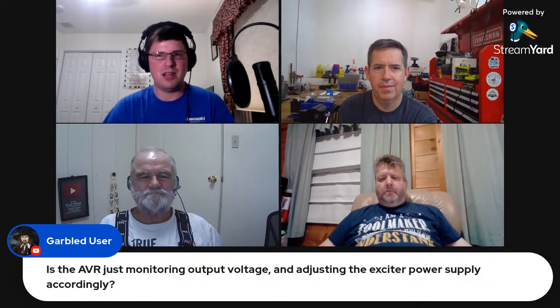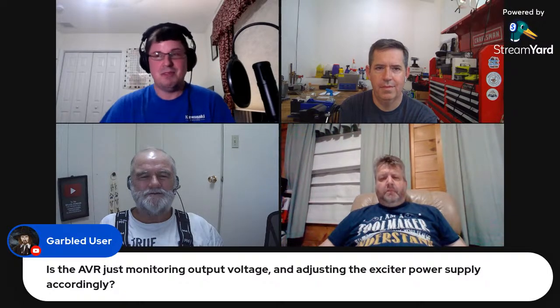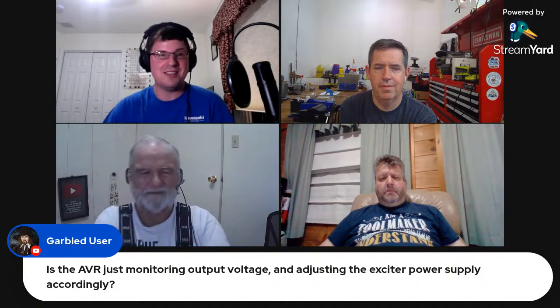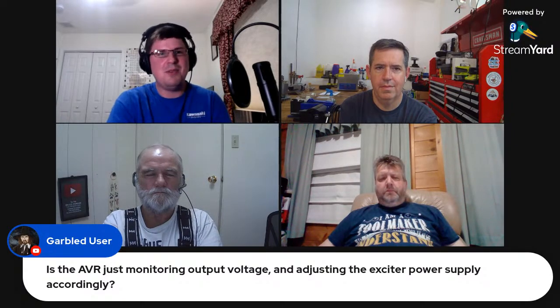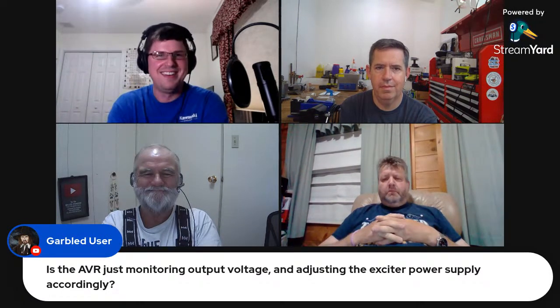There's less moving parts and less wearable items, like you don't have a brush assembly. But in a large megawatt application, look at all the Caterpillar generators of that size, or Kubotas, or any other brand in that megawatt range. They're all brushless. The reason why they have such clean output is because you're not going to put a few thousand watts on it, you're going to put a couple hundred thousand, tens of thousands of watts, and load it down. It's because diesel engines, in order to prevent wet stacking, you have to run them at least 50% load, so that you keep the temperature up in the combustion chamber and you don't get the black smoke coming out of there.